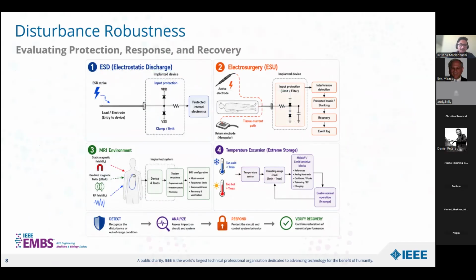So this visual is showing some examples of conditions that require more than ordinary testing. They are different problems, but they follow a similar engineering pattern. The first I'm showing is an electrostatic discharge event, the ESD. The immediate goal here is for the circuit to survive. A transient may enter through the electrode, lead, feedthrough, or any other exposed interface. So the protection network must limit the voltage and divert the current away from the sensitive circuitry inside.